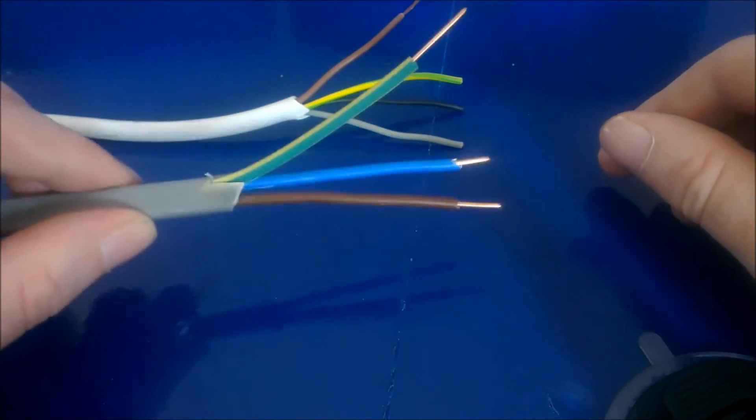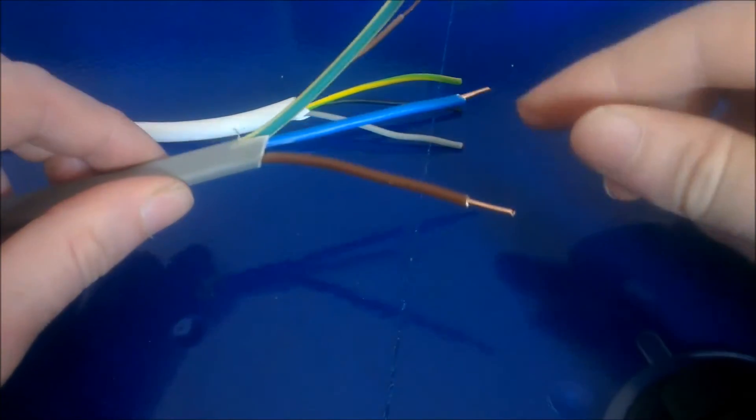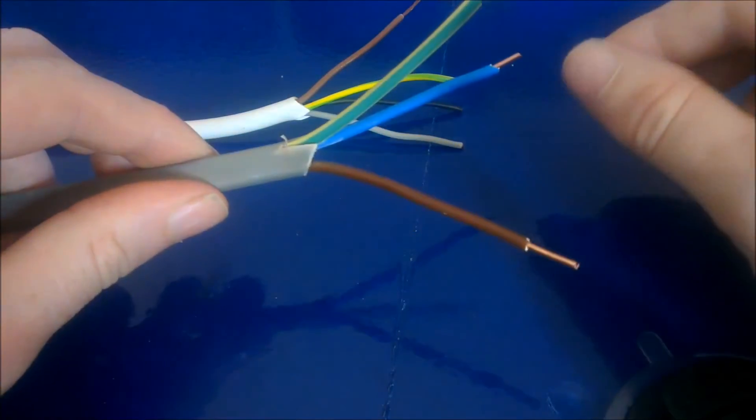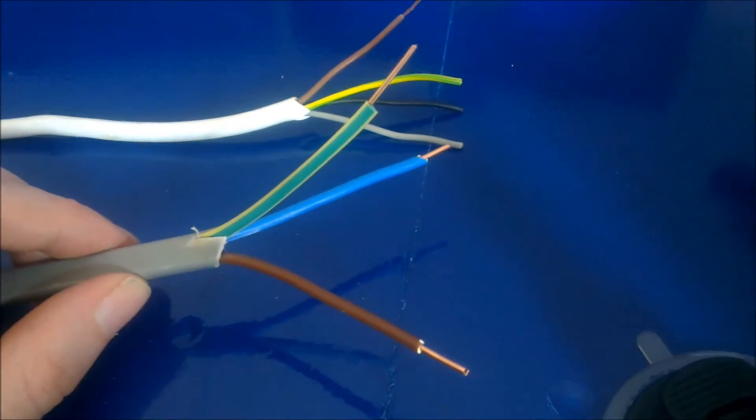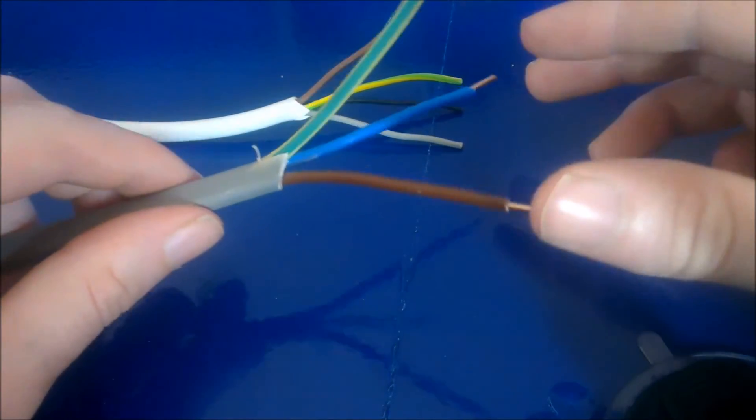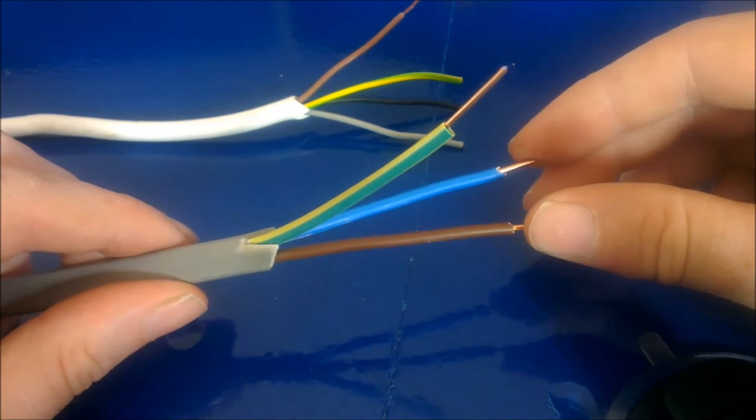So you have two lives in your MCB and your two neutrals will be in your neutral bar, two earths in your earth bar. So a standard ring will come in 2.5mm twin and earth and a 32 amp MCB.